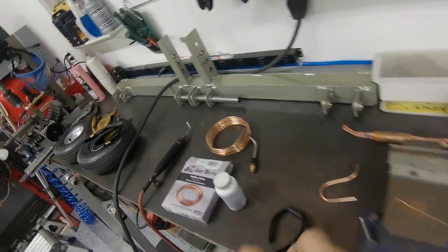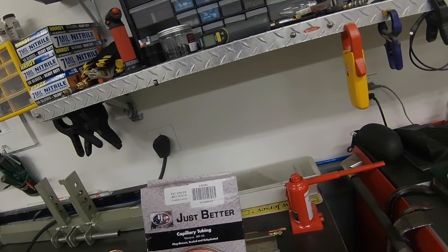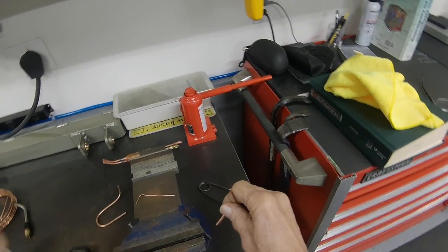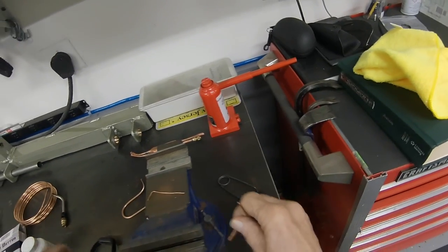So what I got here was I bought this capillary tube, it's a TC-100. It's got a hundred thousandths ID and most capillary tubes that we deal with on subzeros are around ODs about 87 thousandths.